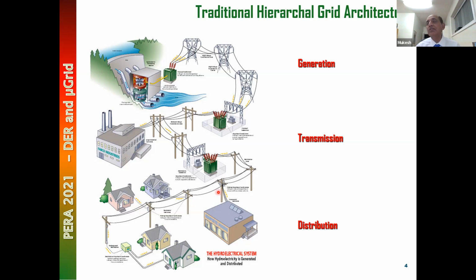And this electricity is sent to the home. Near the home, at least in North America, you'll find it is a 4-wire system. 4-wire means 3 phases, A, B, C, and a neutral wire is the 4th wire. It is 4-wire multi-grounded. The distribution overhead conductor is multi-grounded at many locations. It is not grounded only at the substation. It is grounded about every kilometer or 800 meters apart, like every third or fourth pole. That's the 4th wire. And the loads, your house loads, single phase loads, are connected between phase and neutral through a pole top transformer, which is a phase to ground transformer. This is how the electricity came finally to the distribution system.